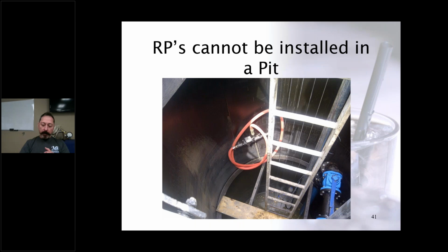Okay, there's a backflow preventer called a reduced pressure principle, referred to as an RP, and it has a discharge port on the bottom. It's designed so that if one of the check valves fails, it will discharge at the bottom of the relief valve port, indicating its failure and discharging any contaminants that could be coming in the reverse direction. Because of that discharge port, an RP cannot be installed inside a pit or anything else.